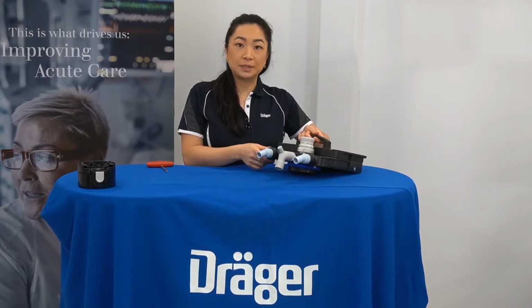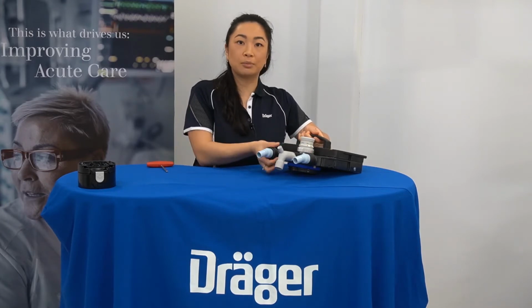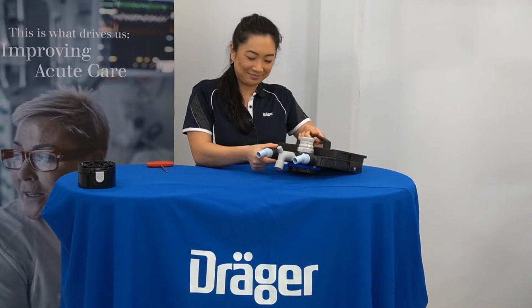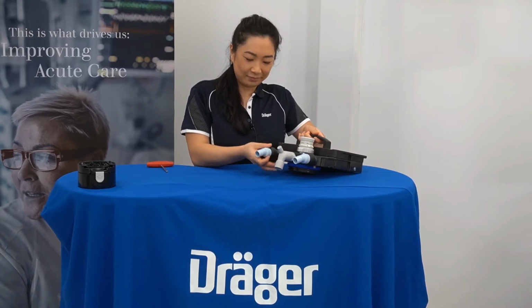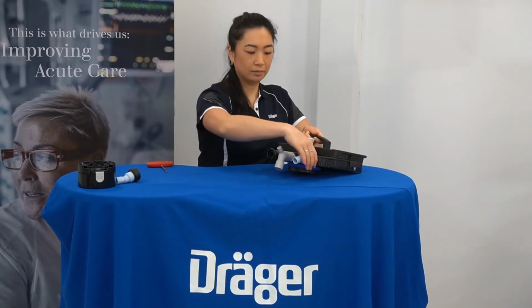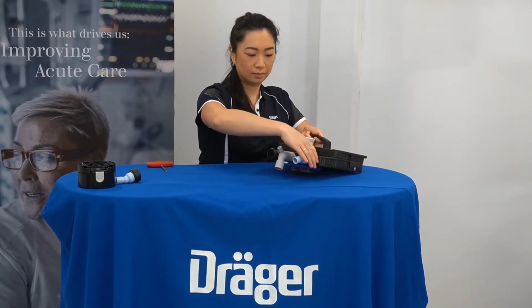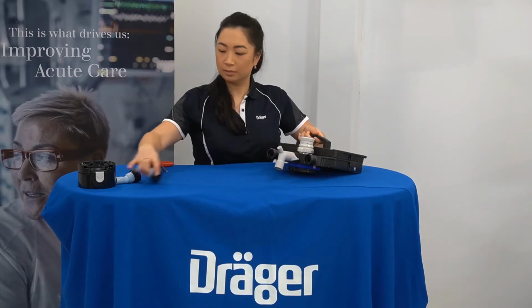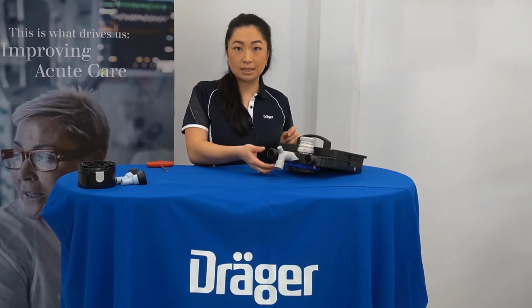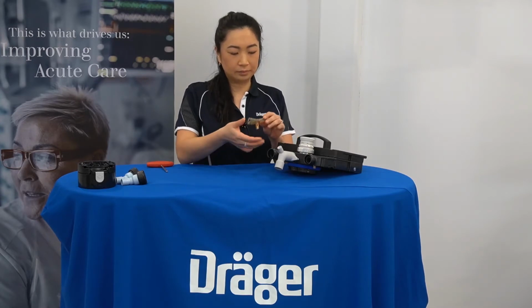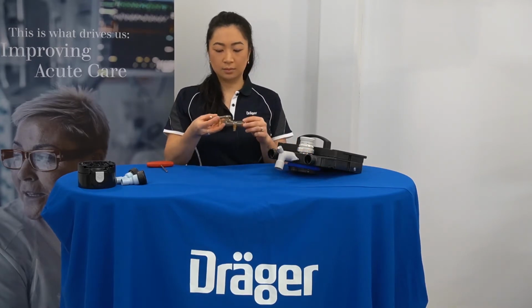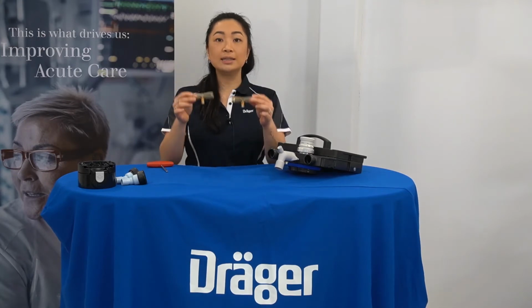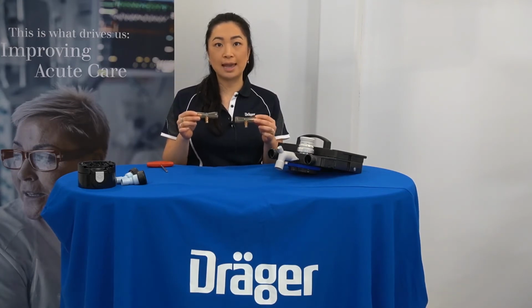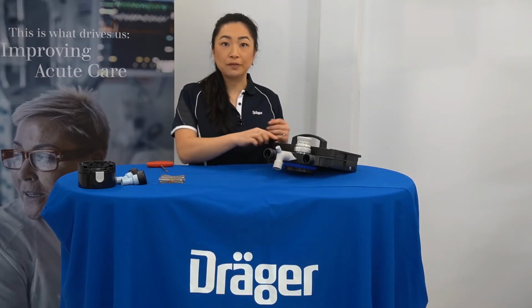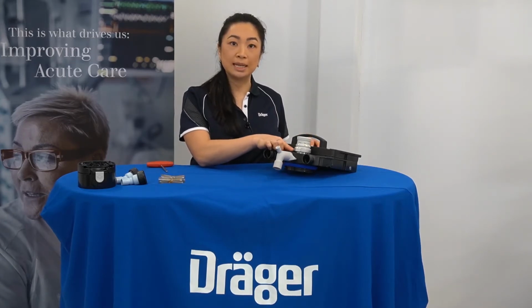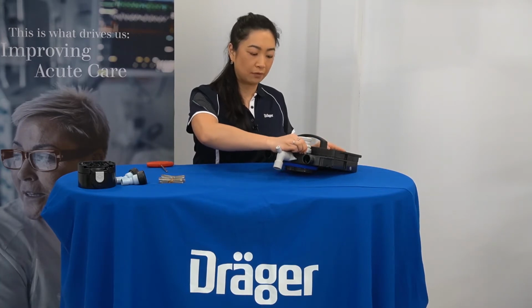Then, to remove the inspiratory and expiratory ports, unscrew the black component at the base. You can now then slide your flow sensors out. These golden coloured Spirolog flow sensors of the Zeus IE can be autoclaved. Now to remove the APL valve. This is done by loosening the bottom grey component of the APL valve.